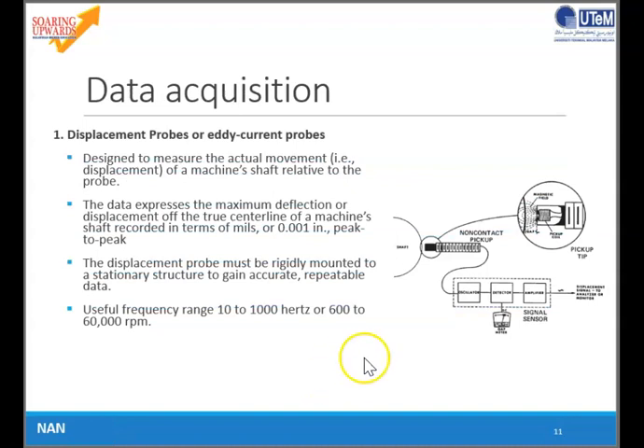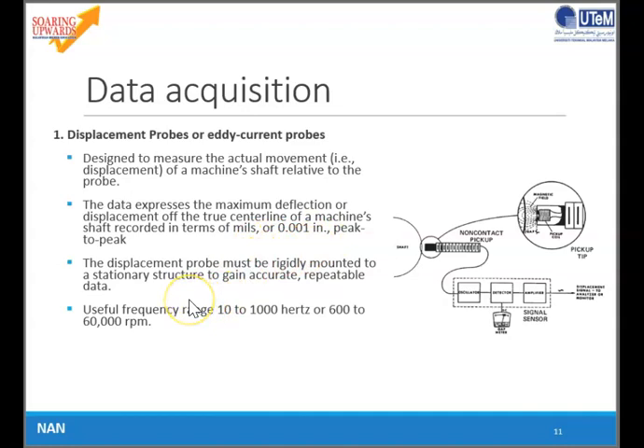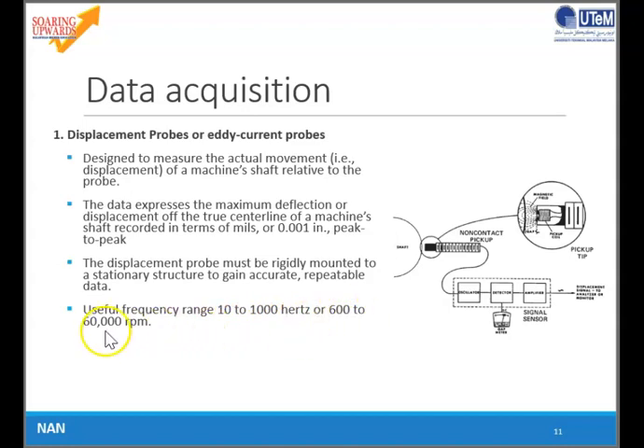Now we will learn about data acquisition. There are three types of measurement for vibration. For displacement, it is designed to measure the actual movement of mechanical parts. The data express the maximum deflection or displacement of the true centerline of a machine shaft, recorded in terms of mils, or 0.001 inches, peak-to-peak. The displacement probe must be rigidly mounted to a stationary structure to gain accurate repeatable data. The useful frequency range is between 10 to 1,000 Hz, or 600 to 60,000 rpm.